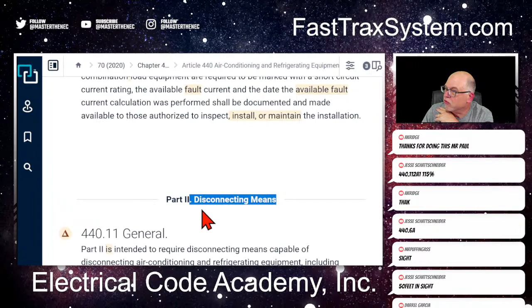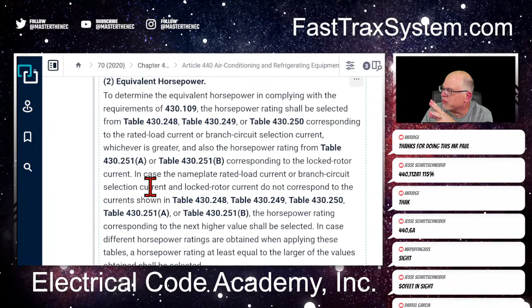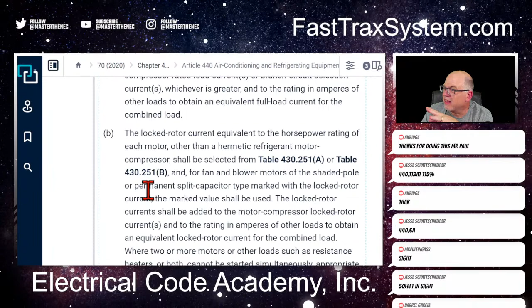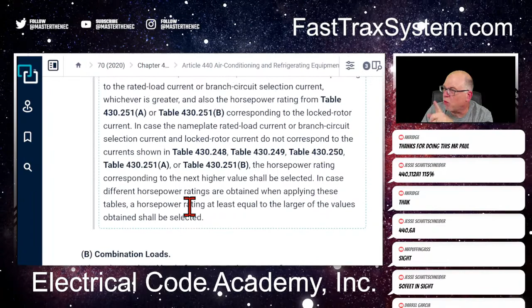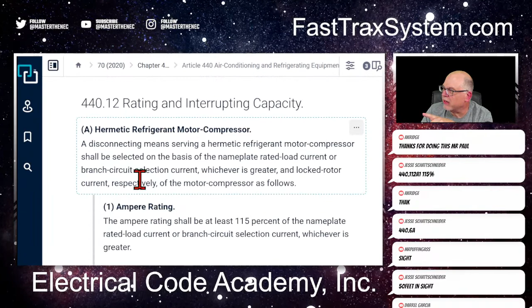So let's go down. So here we're at, and immediately 115 starts sticking out in our head, right? We start seeing that pop up. We don't see the 125, 150, or 200. I'll go down real quick. I see 115 just for scanning, and I'm looking at it. And really it wasn't asking us anything about horsepower, but even if we did go there, it's still 115. So we look at it, but our question is the rating of the disconnect, right? And so that's what we're here, ampere rating, and here's what it says. The ampere rating shall be at least 115% of the nameplate rated load current or branch circuit selection current, whichever is greater. 115%. It's just that easy on that one.